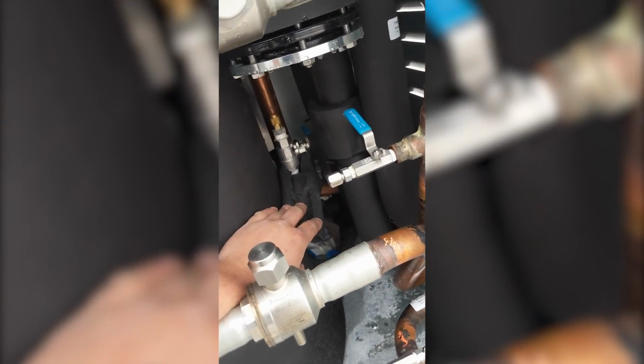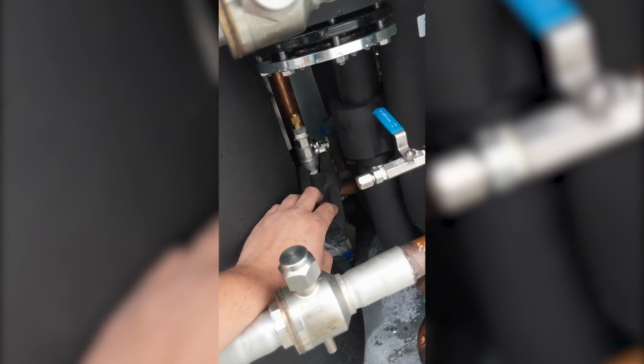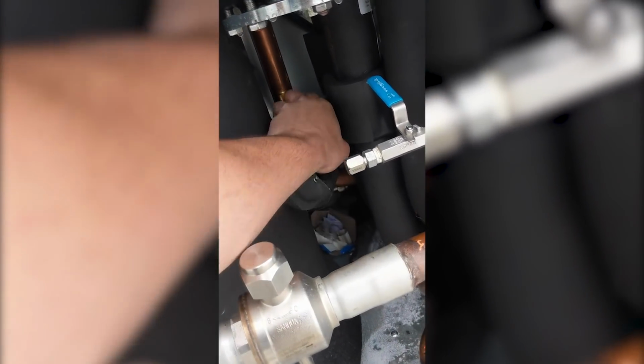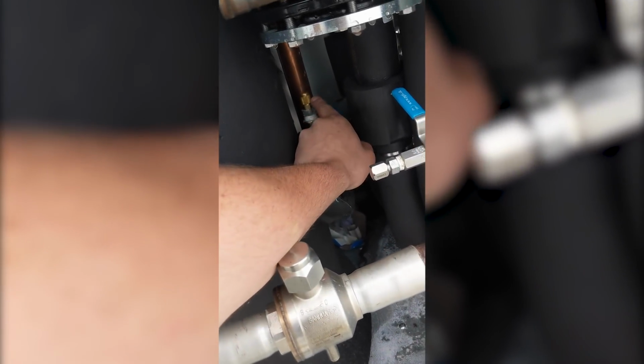And then on this vessel, we're charging in the liquid. It's different. We don't charge in the suction. We're charging in the liquid into the vessel tank. So we have a tap on here and a ball valve. So you hook your line up to this 3/8 tap here.